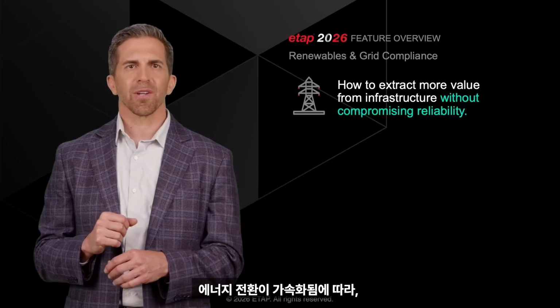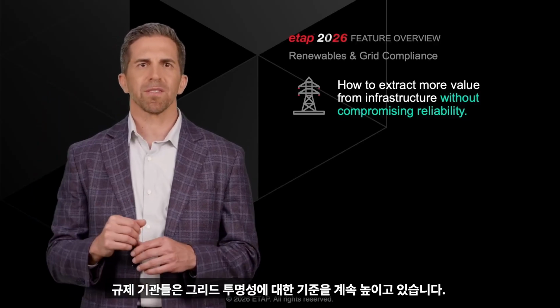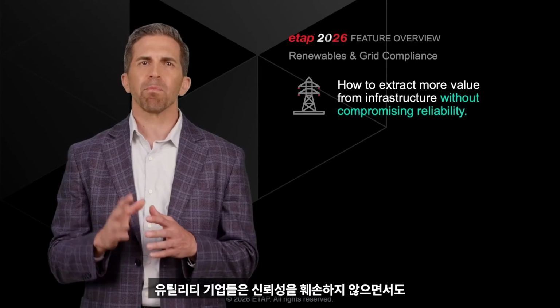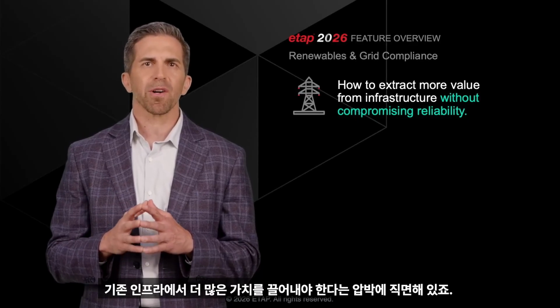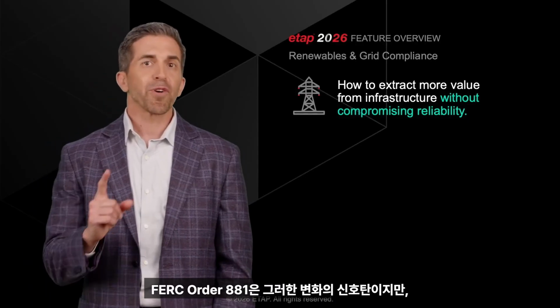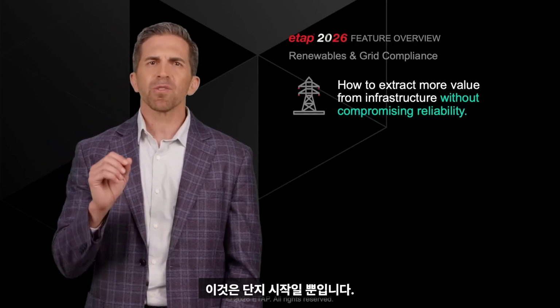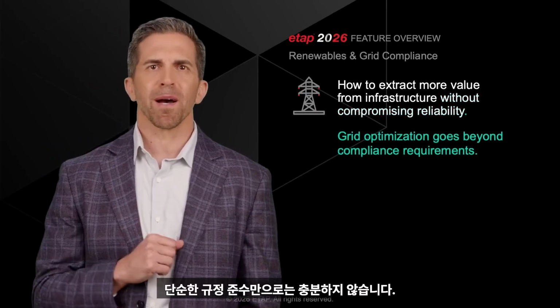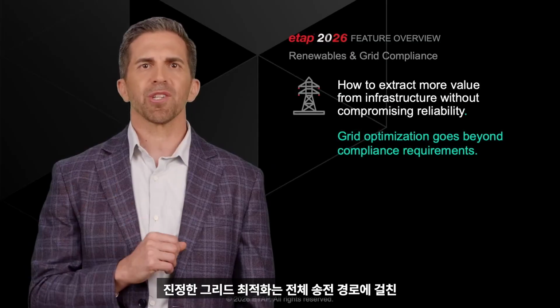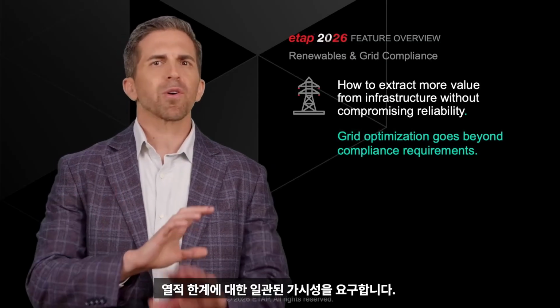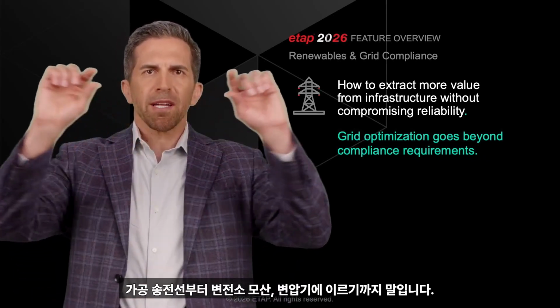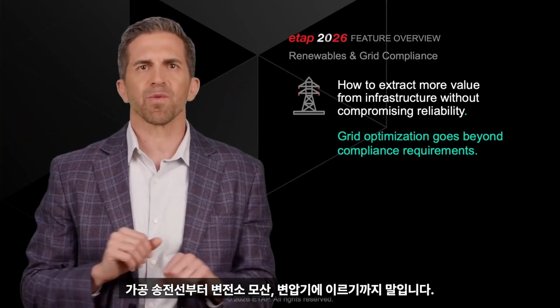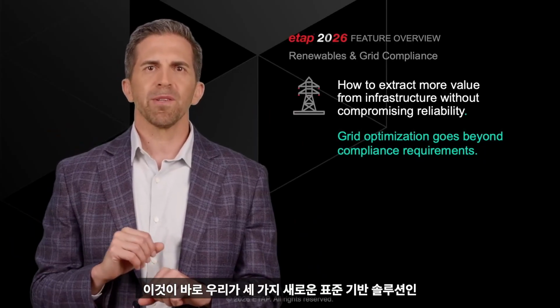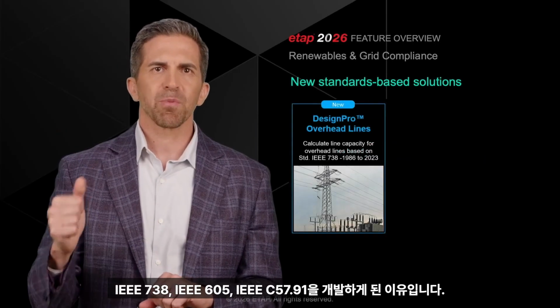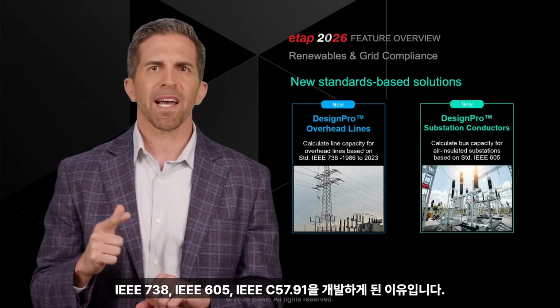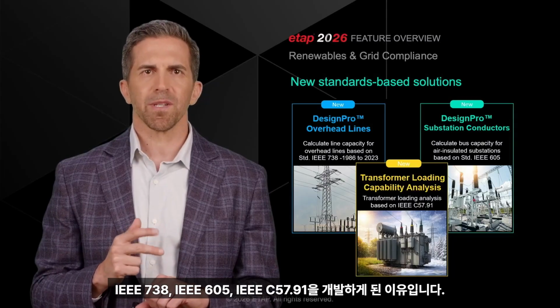As the energy transition accelerates, regulators raise the bar on grid transparency. Utilities face growing pressure to extract more value from existing infrastructure without compromising reliability. FERC Order 881 is a signal of that shift, but it's only the beginning. Compliance alone would not be enough. True grid optimization requires a coherent view of thermal limits across the entire transmission path, from overhead conductors to substation buses to transformers. This is why we developed 3 new standards-based solutions: IEEE 738, IEEE 605, IEEE C57.91.